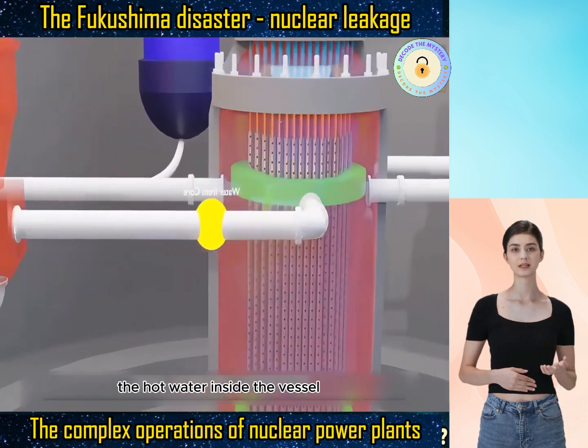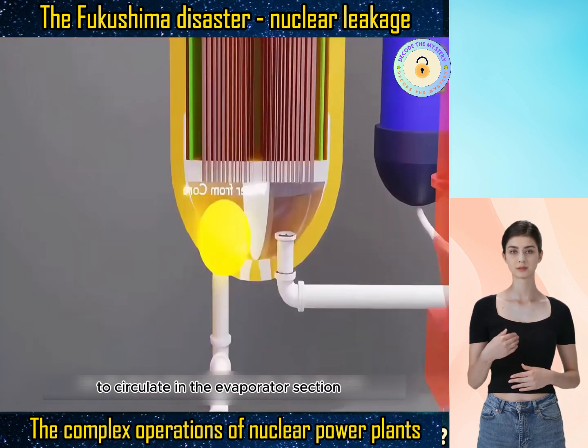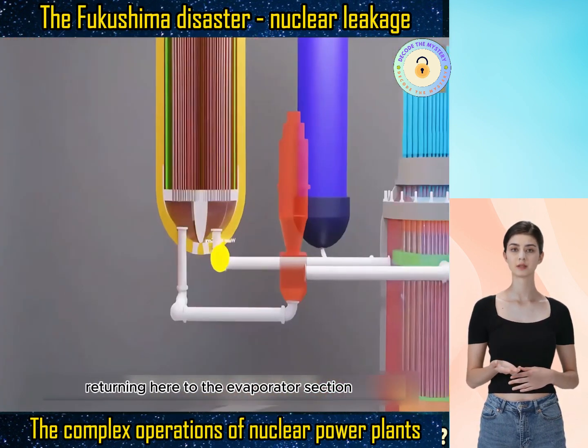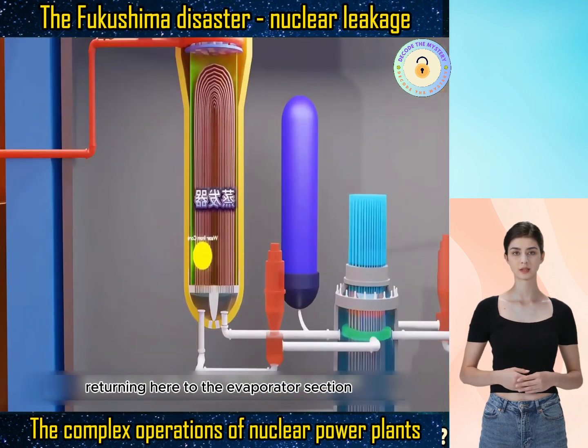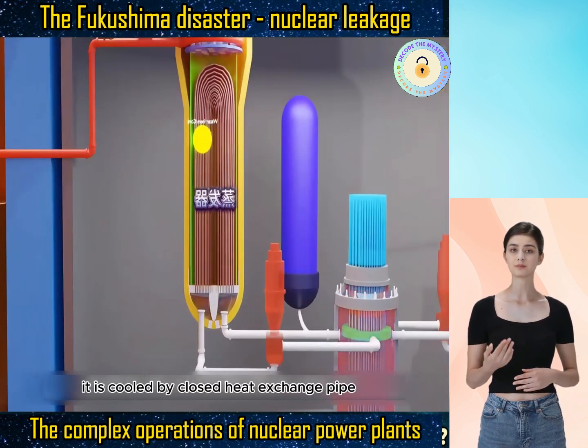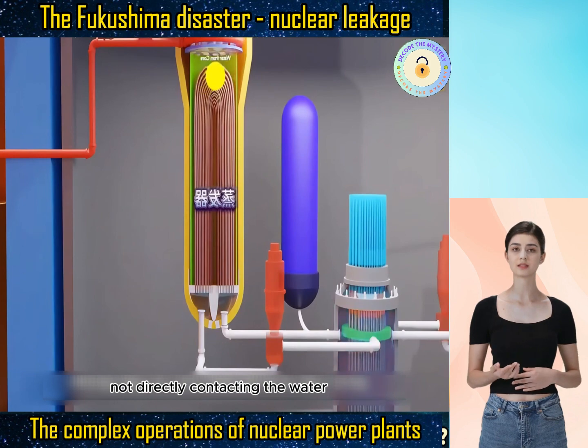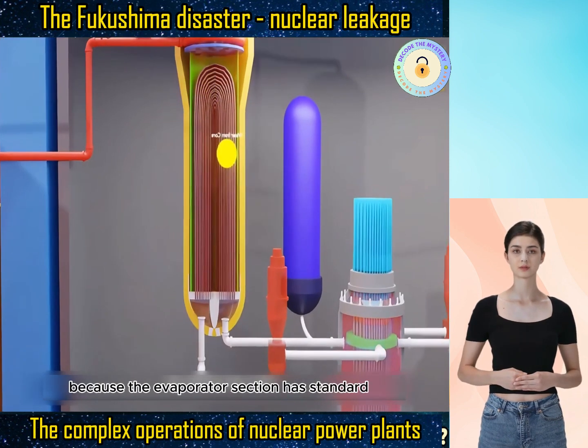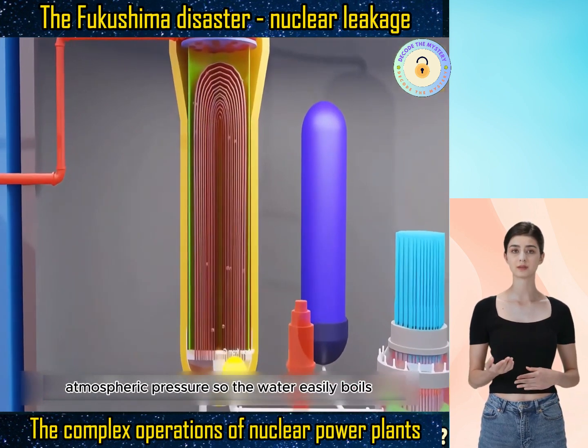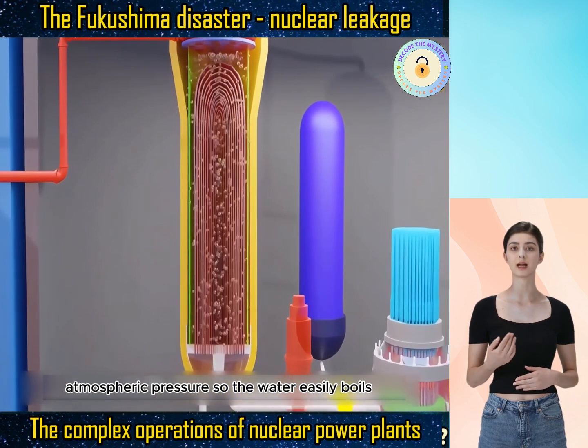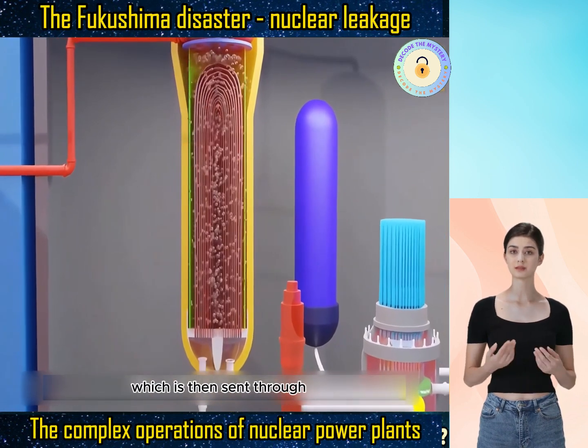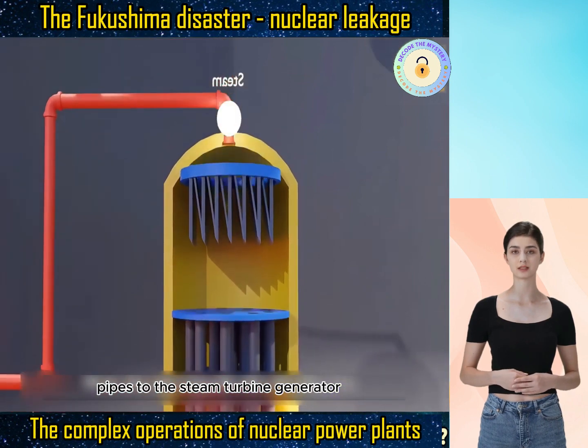The hot water inside the vessel is then pumped through pipes to circulate in the evaporator section, returning here to the evaporator section. It is cooled by a closed heat exchange pipe, not directly contacting the water inside the evaporator section, because the evaporator section has standard atmospheric pressure, so the water easily boils, creating high-pressure steam, which is then sent through pipes to the steam turbine generator.